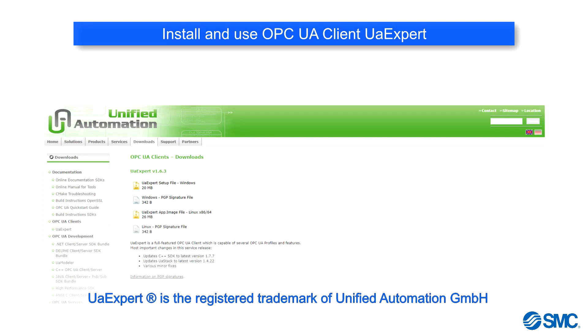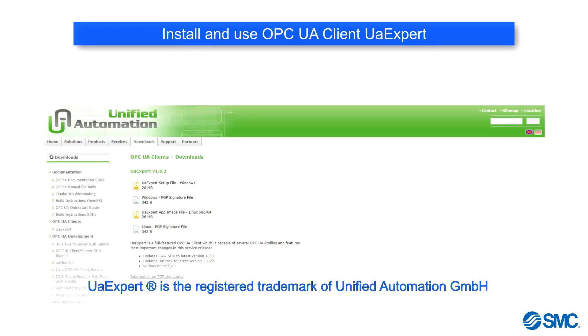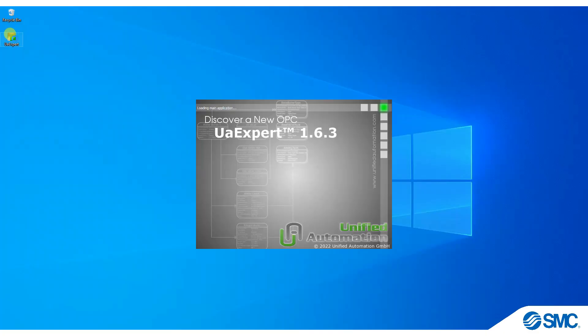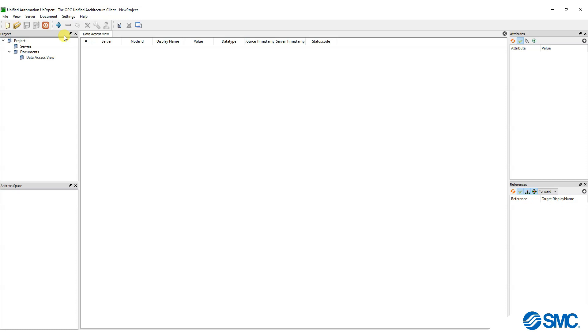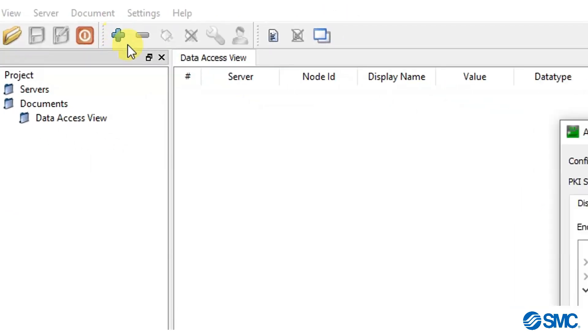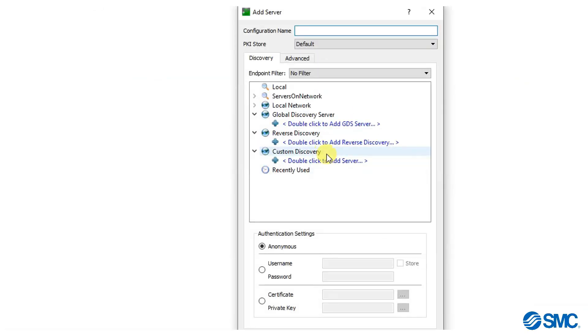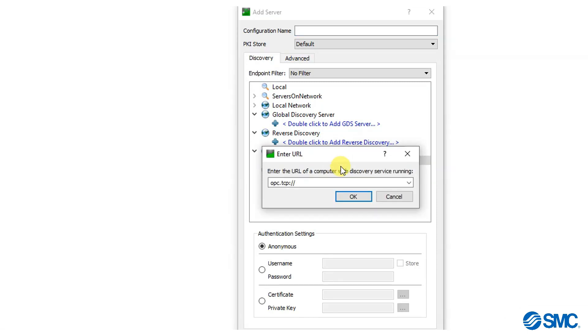In our example, we are going to use UAexpert as the OPC UA client. We will now demonstrate how to connect to the OPC UA server. Open UAexpert and click on the plus symbol. Locate custom discovery and double click on add server. Enter the URL and IP address, then click OK.